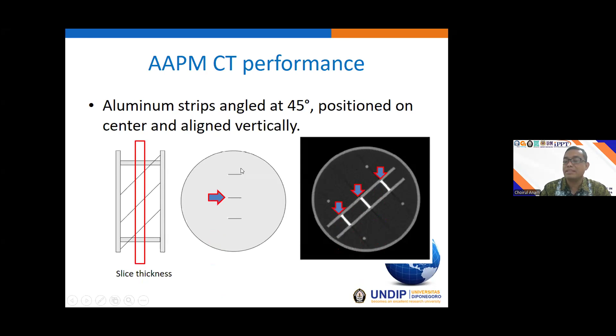Okay, and this is the 3 objects. This is the diagram in the z-axis, and this is the example diagram in the axial plane, and this is the real image, an example of the real image of the module from the AAPM Phantom for measuring the slice thickness. And this is, for example, the position of the beam for measuring the slice thickness, and this is the object obtained in the axial image. We have the 3 objects here, and this is the real example of the Phantom. And this is the process of how to automatically measure the slice thickness.